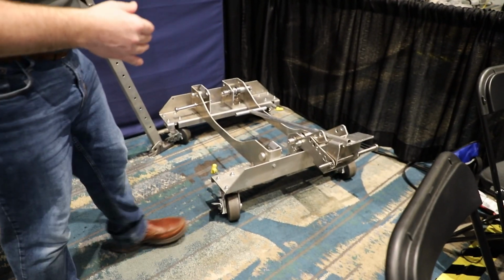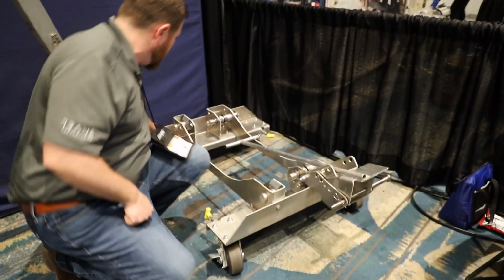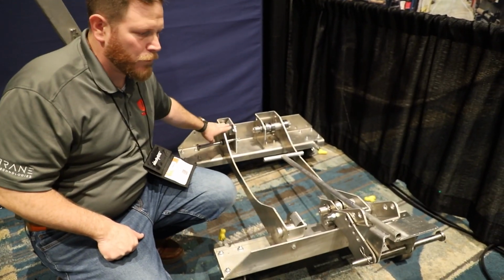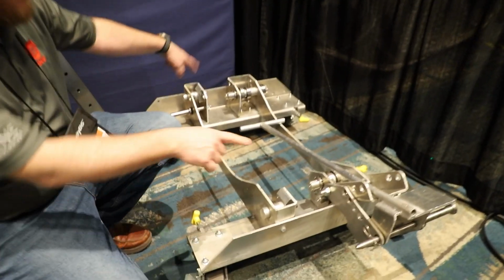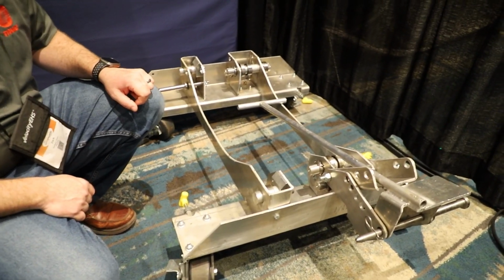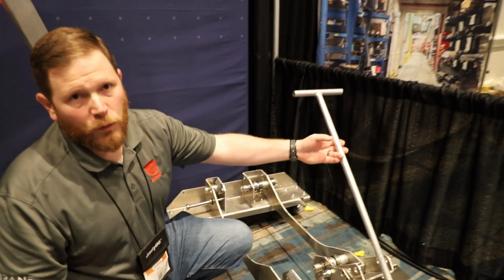So we designed this cart so that when the casing is removed from the chiller, it can be dropped directly into this cart. They put a pin into the volute here that holds it securely in place, and then with 4 360-degree swivel wheels, they can utilize this handle to roll the cart anywhere they need to in the machine room with minimal effort.